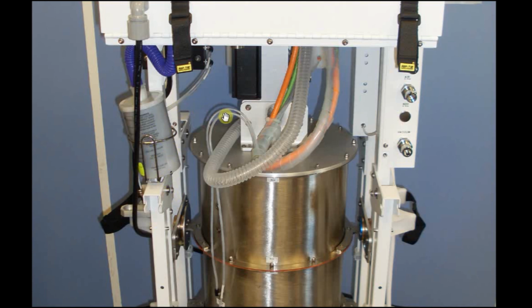Conversely, if the machine or the patient circuit senses a negative pressure in the patient circuit that falls below -8 centimeters of pressure, in other words it's more negative than -8, then this dump valve, or the dump valve that you can't see up in the machine that connects to this manifold, will open and allow fresh air to come in through the air filter, therefore being filtered, and then up into the patient circuit, so that the patient cannot see a negative pressure of greater than -8 centimeters of water.